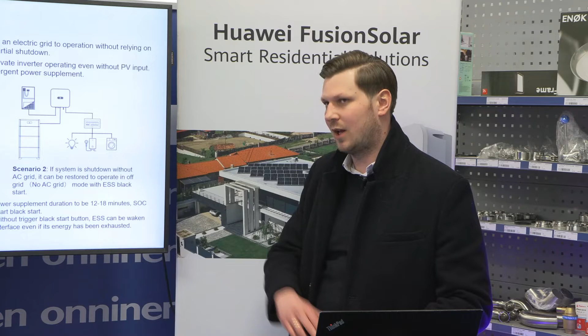So if you're using the battery inside, it's fine, but if it's outside, I would not recommend setting it to zero for a long time - a week, or during winter time when we don't have sunshine, maybe 2 or 3 weeks. During winter time, I would suggest changing the minimum SOC to like 10-15%, not keeping it at zero. It's like with cars - you can use a car for 10 years without problems, but if you drive very rough, after 2 years you'll have to replace half the components. It's the same with a battery.